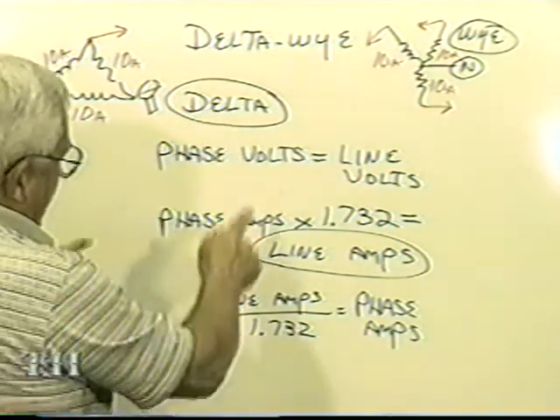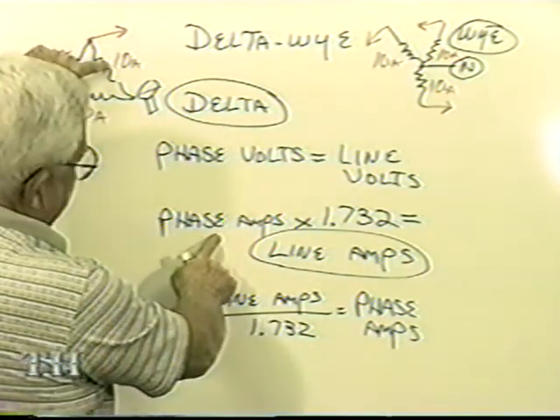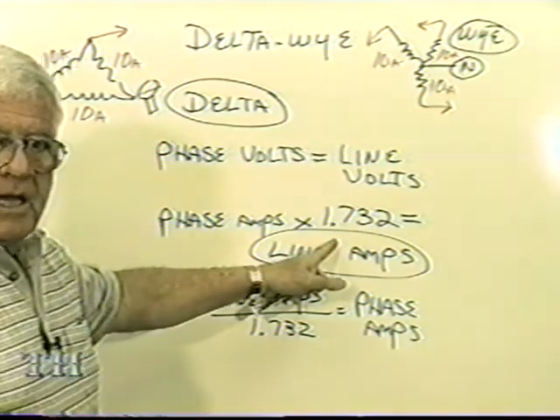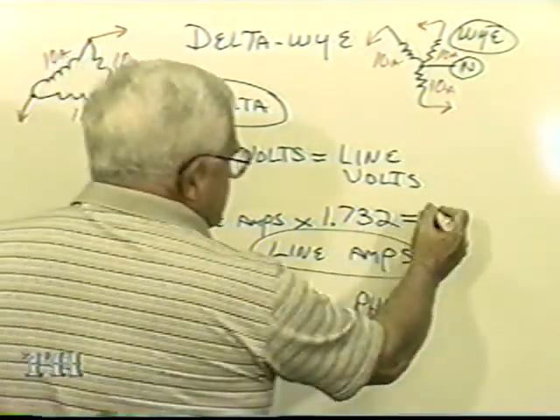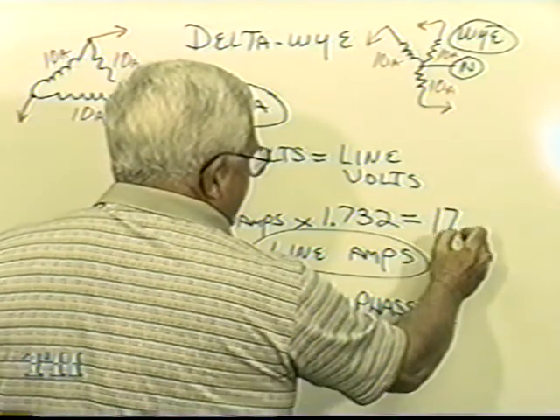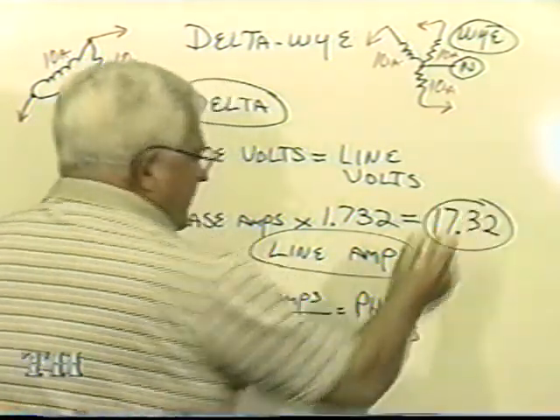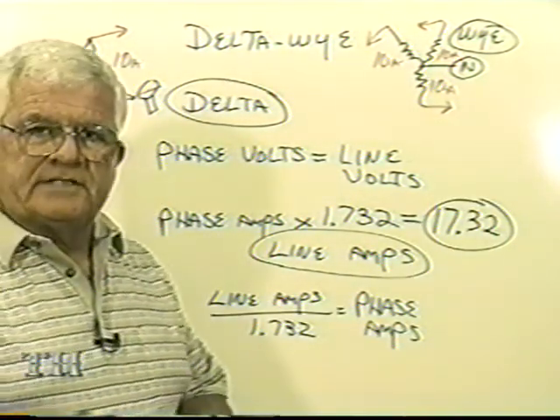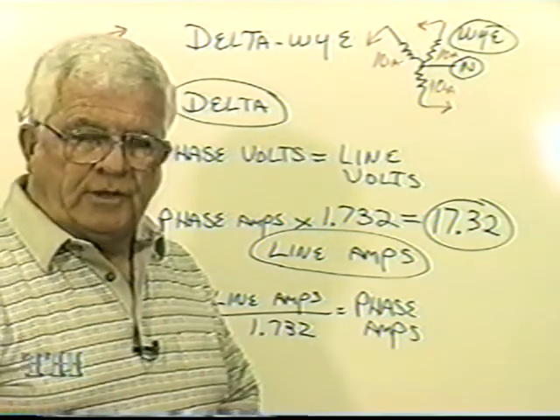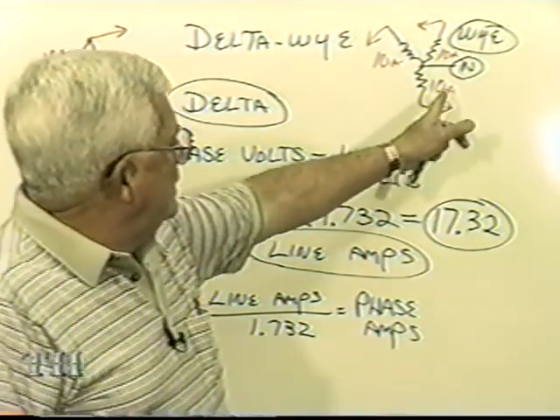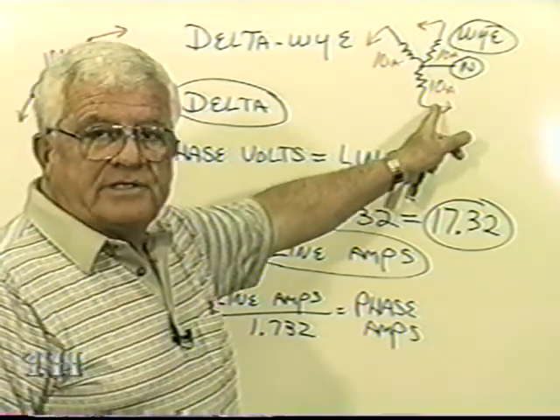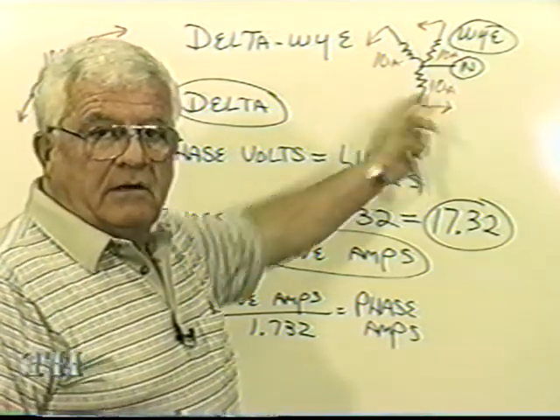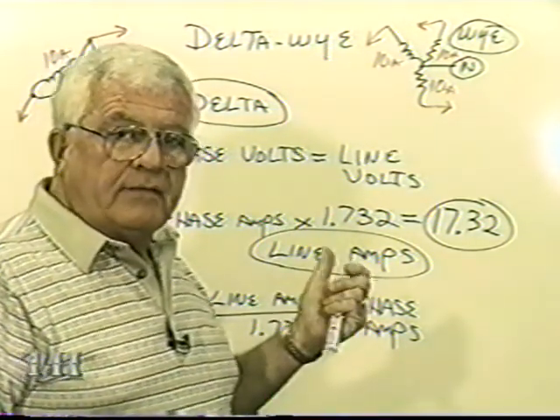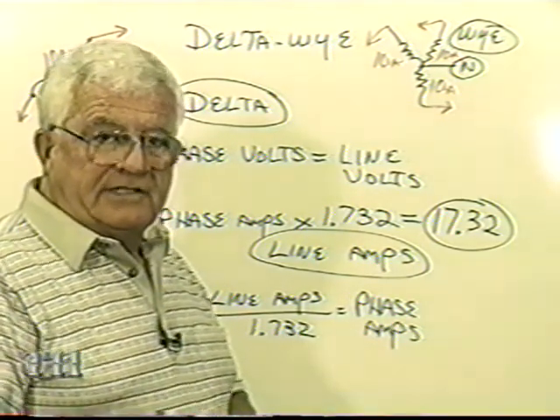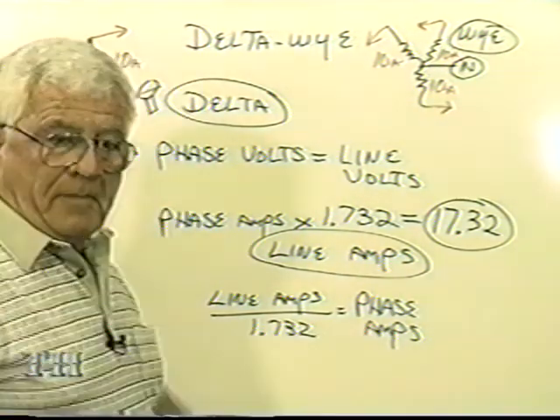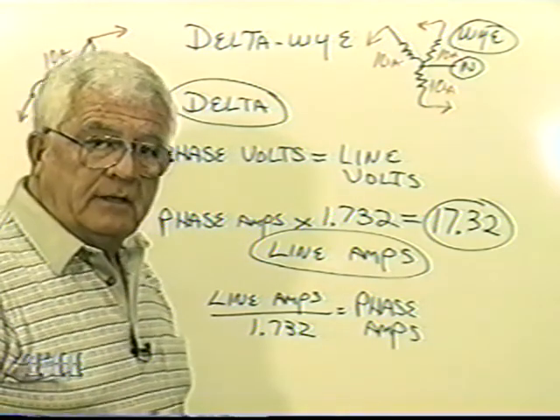If it's a delta, I come right here and I say, well, the phase amps are 10. I'm going to multiply it, and I'll have 17.32. That's what my meter is going to read. That's going to be my line current. Over here, if I put an amp clamp there, it's going to read the same as a coil, 10. Over here, it's 17.32 amps. That's our picture, that's our format that you have on sheet 1.